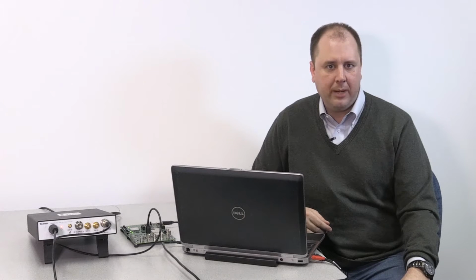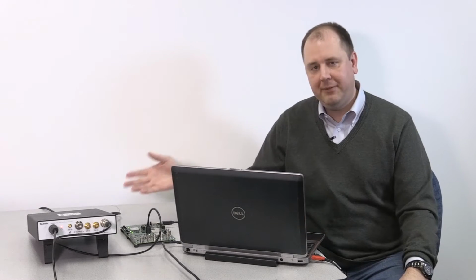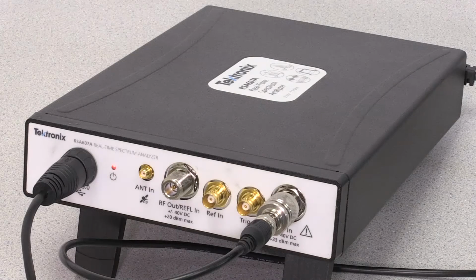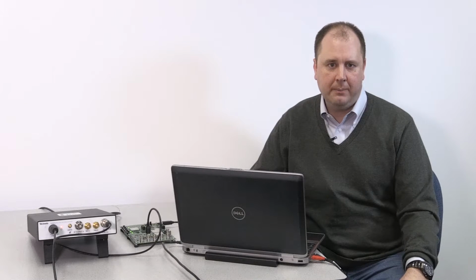And this is a quick how-to video for testing Bluetooth RF physical layer parameters using the RSA-607A. It's a Tektronix real-time spectrum analyzer, which is controlled through USB to a PC running SignalVu-PC software. Now, there's two basic kinds of Bluetooth parametric testing for physical layer.